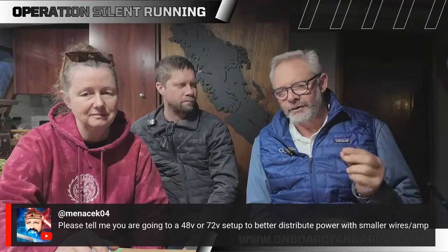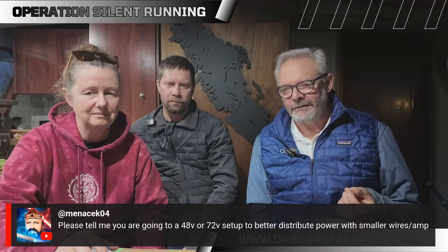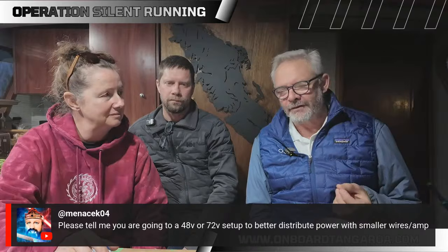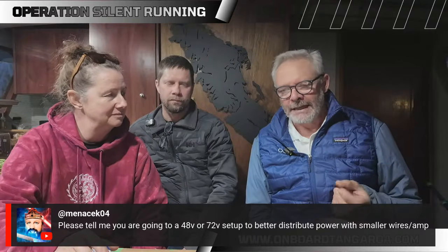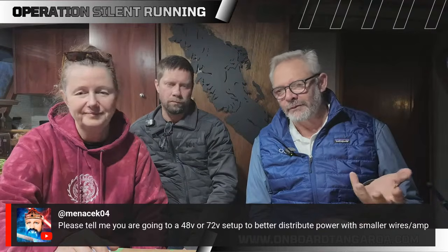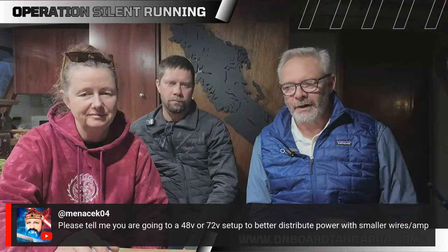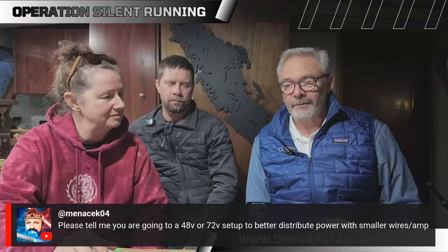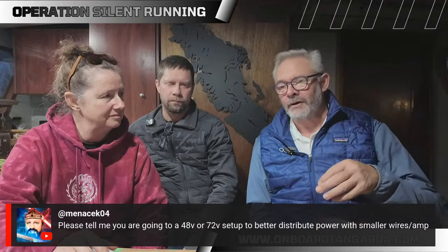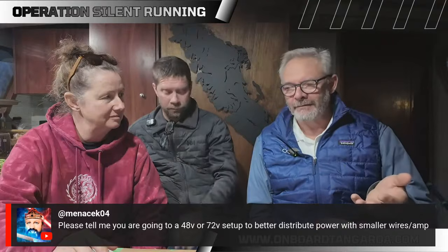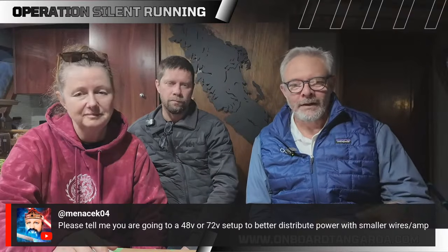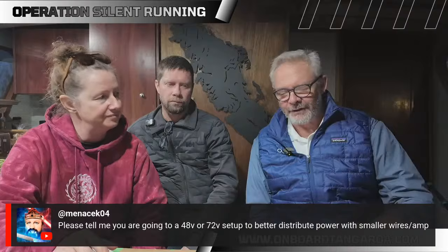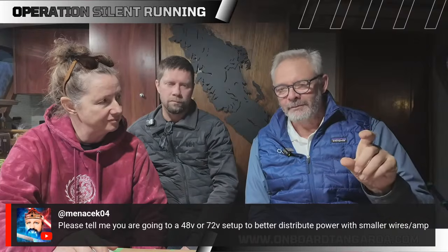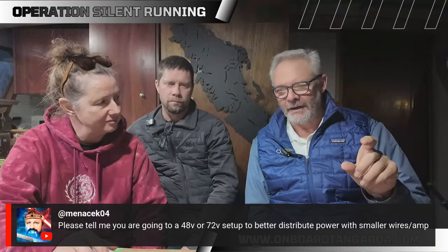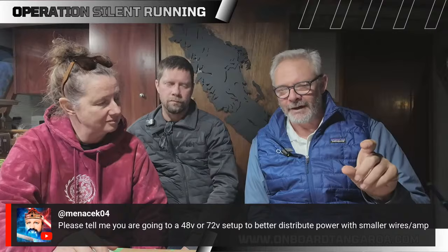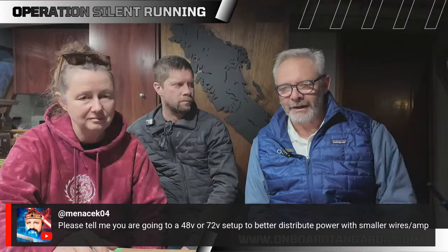To get the kind of power we need for these systems from the batteries, you have to go to a much higher voltage. That allows us to use, probably, a 2-aught cable for a lot of the battery-to-bus-bar power. On my 48 volt system on Karma, I have to use 4-aught cables and solid copper bus bars because I'm drawing 800 amps max, and 800 amps at 48 volts is a lot of heat.